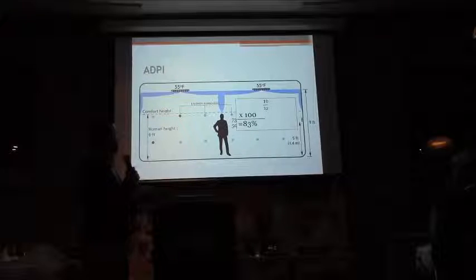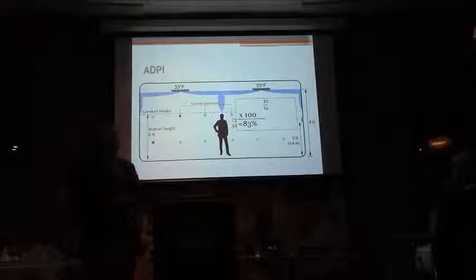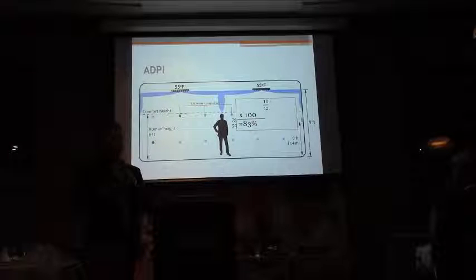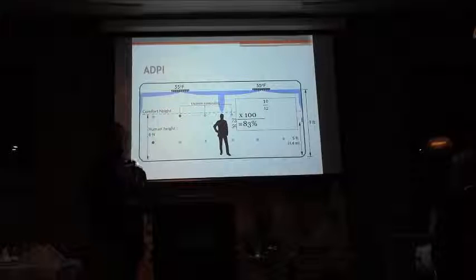And the second challenge is that it's only valid in cooling mode. So that's great for areas like California where you're cooling all the time. But here in Canada, we're approximately heating half the time, cooling half the time. So in reality, half the time, we have no idea what's going to be the efficiency of our HVAC system.